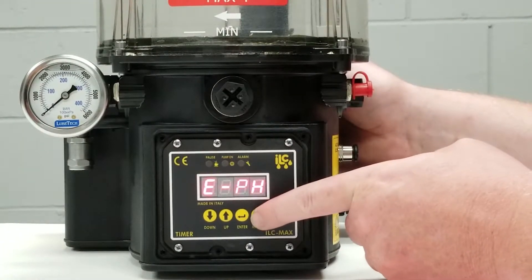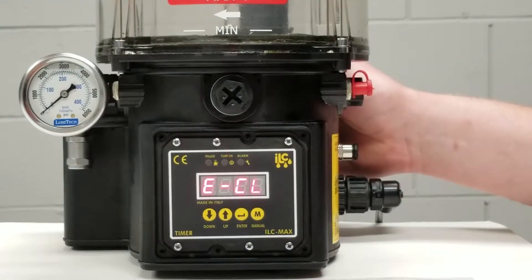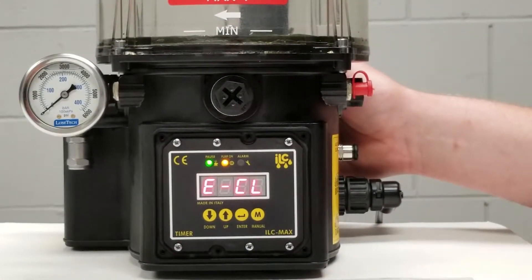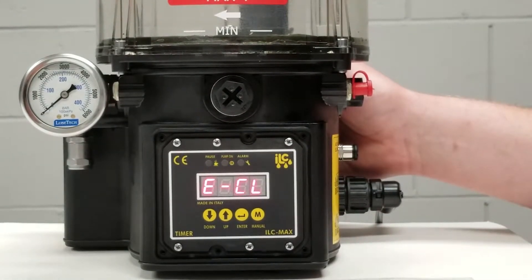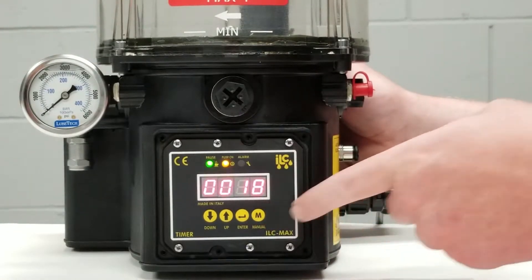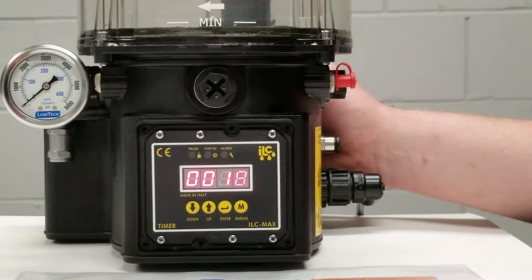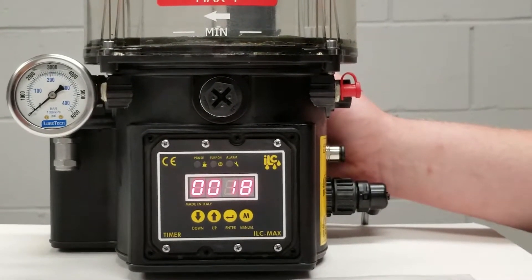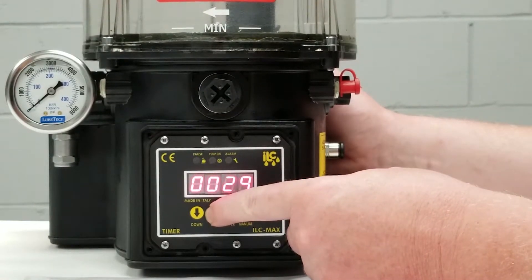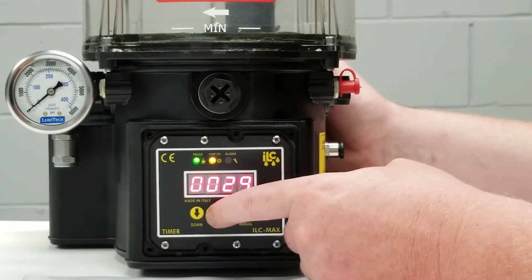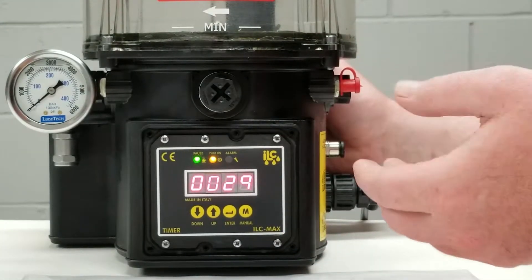We'll go back to our programming menu and this particular pump is set up to pump and rotation count. E-CL will tell me how many rotations this pump is set for. Again we're going to press our M button to enter that parameter and see what the setting is. So this particular pump is programmed for 18 rotation counts. The higher the rotation count, the more lubricant it will deliver. The lower the rotation count, the less lubricant it will deliver.